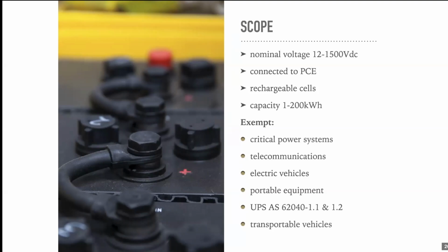So we didn't actually want to try and capture large commercial and utility scale battery storage. So 200 kilowatt hours was kind of the upper limit in this scope. But I should point out that it's really only a recommendation. Any entity that requires compliance can choose for you to comply to the standard as well. So you might be installing a commercial energy storage system that's half a megawatt hour, and the utility might say, we want compliance to the standard. So don't think you escape just by being out of scope.